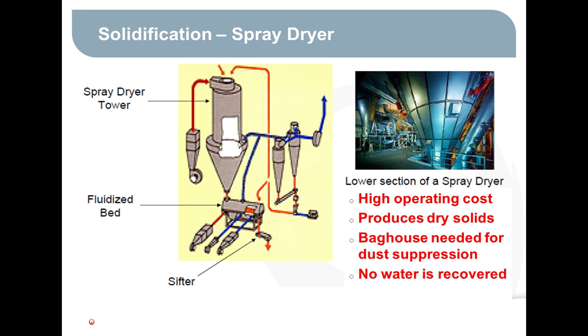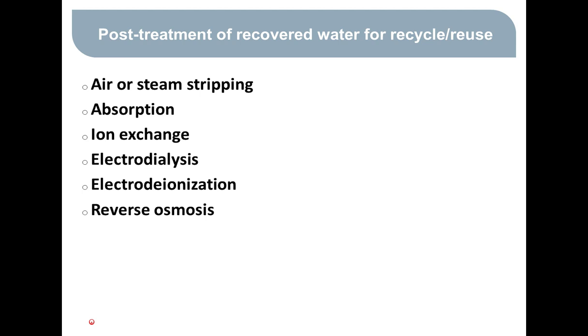Also, you don't get the water back. It basically gets vented to the atmosphere. So, finally, when we are looking at the recovered water, whether we use evaporators or crystallizers or RO for that matter, when we recover the water in our ZLD scheme, it may have some things in it that we don't want, especially if we're going to reuse the water. So sometimes we have to do some additional treatment on the recovered water itself, especially if you have volatile components which could wind up in that recovered water. Things like volatile organic compounds or ammonia or volatile solids like boric acid. Those things tend to wind up in the recovered water.